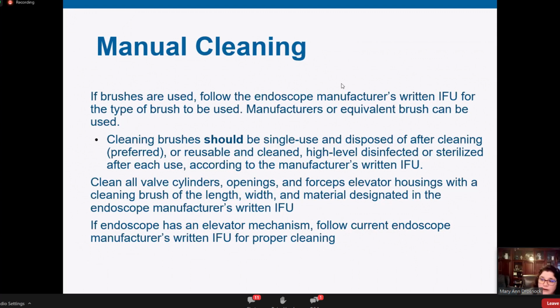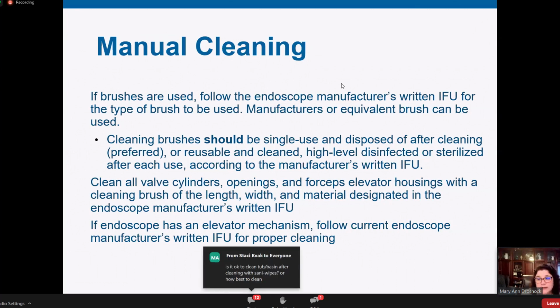Okay, I see a question for clarification. Wet leak testing is 60 seconds. Yes, that is true. And as far as dry leak testing goes, follow your instructions from your dry leak tester manufacturer to know what to do for those. The 60 seconds is definitely for the wet leak test. If you can get that instruction from the IFU for the dry, that would be the best case.